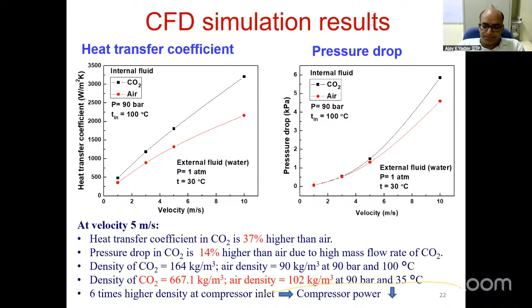Even if you keep the velocity the same, there is the density difference. I'm comparing the density of CO2 here: in the third line, the density of CO2 is 164, whereas air density is 90. On the suction side of the compressor, CO2 density is 667 and air density is 102, at the same pressure and temperature, 90 bar. So you get about 6 times higher mass flow rate. This is a big achievement: with almost the same pressure drop, you get 6 times higher mass flow rate. So the size of the heat exchanger will also reduce. That is what I meant to say here.